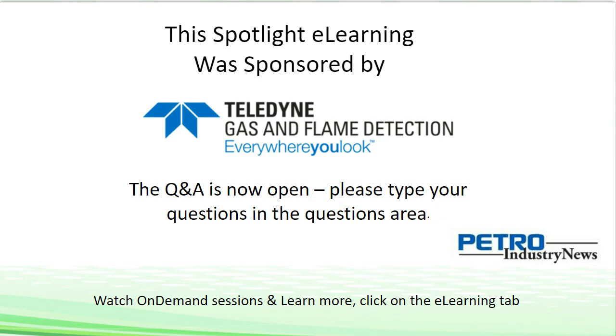So, Francois, I'll say a few things. Perhaps you might also have some comments. Locating a fixed gas detector or a mobile, transportable gas detector close to a maintenance team, or where you wear it on your clothing, the location of a gas detector is really very important. And typically fixed gas detectors are placed in areas of a plant facility where a leak is most likely to happen. For example, over a gas compressor, or over a flange, or over a valve. And in terms of answering the question, how can we be absolutely certain that the gas detector will pick up the leak? Well, perhaps the wind is blowing very strongly in a direction that's blowing the gas away from the detector. Of course, these things are possible.